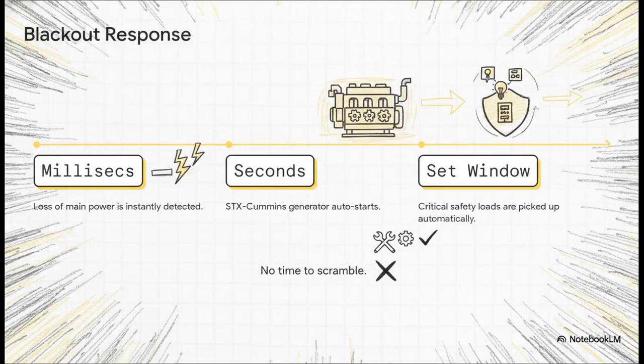And because it's focused solely on survival, the timeline here is incredibly fast. The moment a blackout hits, within milliseconds, the system detects the loss of main power. Within seconds, that STX Cummins generator auto-starts, and then within a strictly defined time window, critical loads are picked up. All of this must happen automatically. If an emergency generator fails its scheduled automatic start test, it defeats the entire purpose of the system. In a real blackout, there's just no time to scramble.